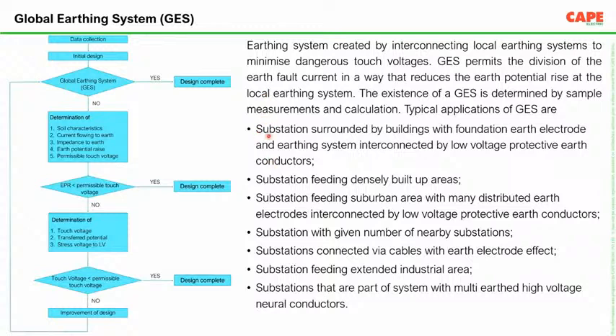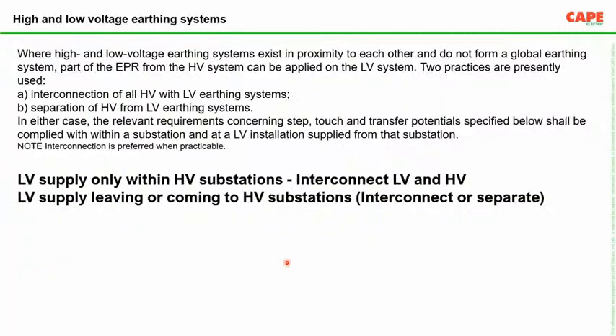Global earthing system can be used in substations surrounded by buildings with foundation earth electrodes interconnected by low voltage protective earth conductors, substations feeding densely populated areas, substations feeding suburban areas with many distributed earth electrodes interconnected by low voltage protective conductors, and substations with a given number of nearby substations. This global earthing system will not work for an isolated installation. If you are in a city center, where a lot of steel or metal installations are there, then we can go for global earthing system, and this is the one recommended in industrial systems.